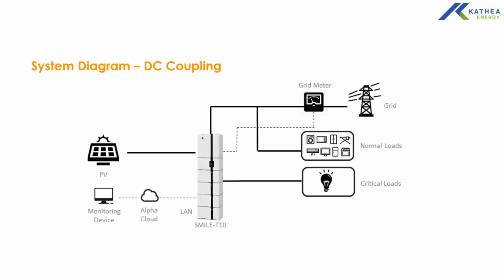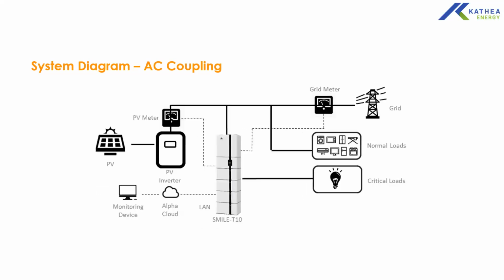So the system working mode is the same as that of SMILE5. The normal system with one inverter with PV to the inverter is a DC coupling with your grid meter, your normal loads and critical loads. And then if you have a second inverter without PV connected to the alpha, the system is an AC coupling. You would need a second meter wired to the inverter.